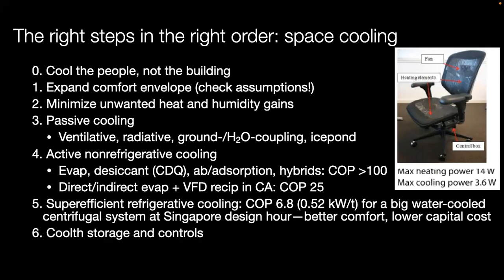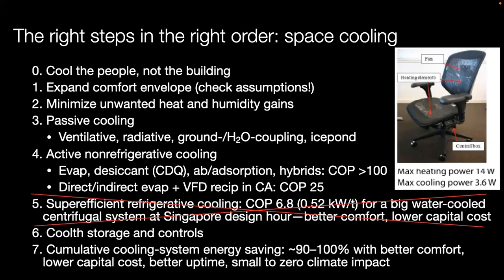Next, if needed, would come coolth storage and controls. But actually, we need never get as far down the list as refrigerative cooling, or probably even step four, to save 90 to 100% of the cooling energy with better comfort and uptime and lower whole-system CapEx, even in the most severe climates. Most practitioners pursue these options in reverse order, worst buys first.